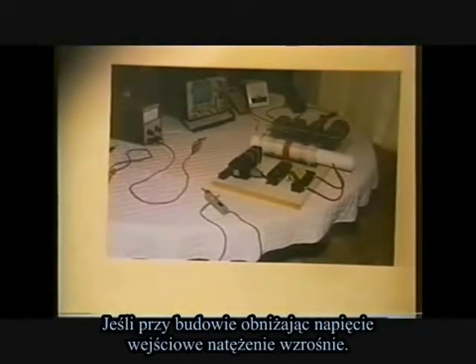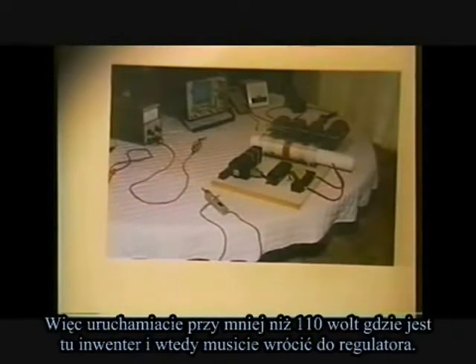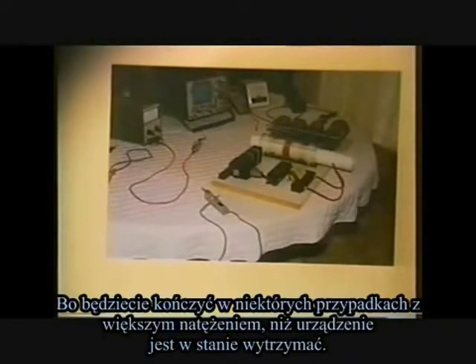As a matter of fact, as you lower the voltage in, the amperage goes up on this thing. So if you run it at less than 110 volts on this inverter, and then back it off again with the variable deal, you're going to end up with, in some cases, more amperage than the device can handle.